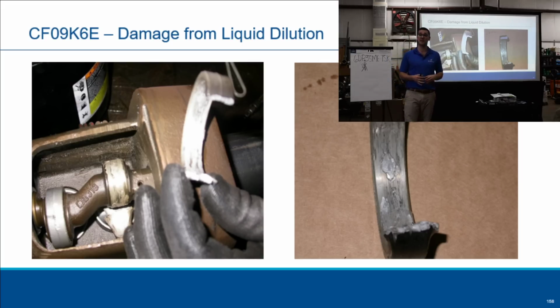Put them back inside. On scrolls, on the other hand, you want to talk to your distributor first before you cut open a scroll. If you know it's way out of warranty, if it's a 5-year-old compressor, that's out of warranty for sure, right? But if it's close or it's in warranty, contact your distributor and say, is this an in warranty compressor or not? If they say it's not an in warranty compressor, cut it open. Okay? If it's in warranty, I would talk to them. Guys can cut them open if they're still in warranty, but you want to verify with your distributor first if they need it back to check it, to inspect it.